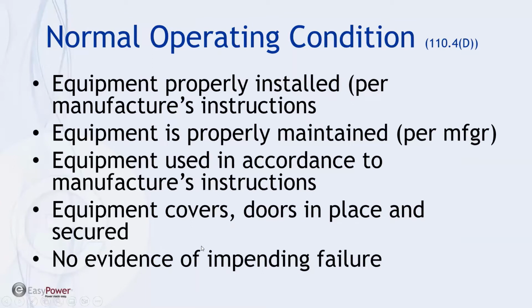Now, the basis or background of assumptions for applying the recommendations in NFPA 70E is what's defined as normal operating conditions. This includes that the equipment must be properly installed per manufacturer's instructions, properly maintained per manufacturer's instructions, and used in accordance with manufacturer's instructions. The equipment shall have covers and doors in place and secured. And probably as important as anything else, there's no evidence of impending failure. The bottom line is, if we can't answer each of these in the affirmative, we need to make sure that we understand how that affects the calculations that are being done or the hazard assessment that's being made, in terms of our need for maintenance.